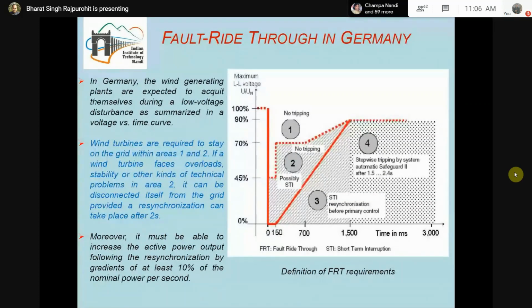Below this right-hand side red line, the wind farms can disconnect slowly from the grid, but in a phase-wise manner, if the voltage is still below this red thick line. So this is the requirement for fault ride through. But you can see zone number 2. In zone number 2, we see that a certain relaxation is there: the wind farms should not get disconnected, and short-term interruption is possible, but no tripping.